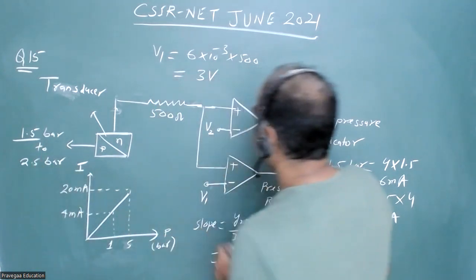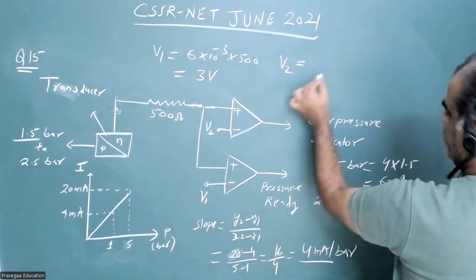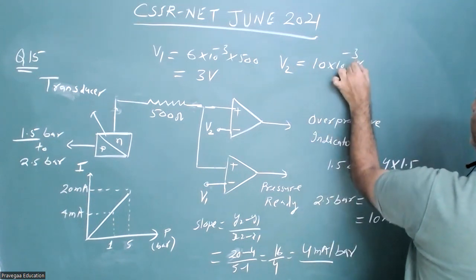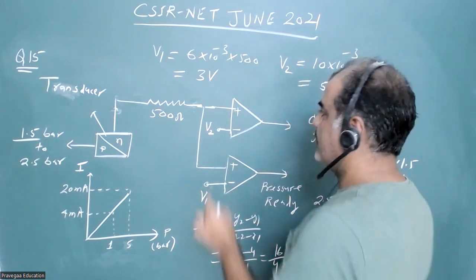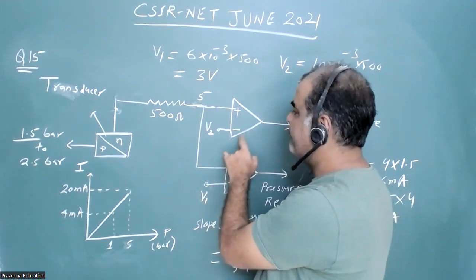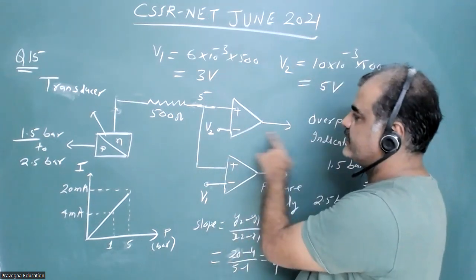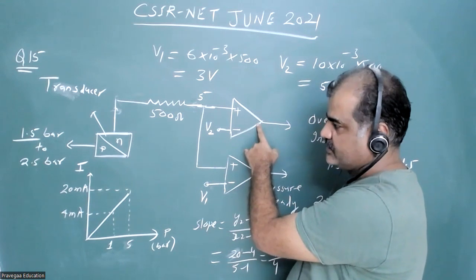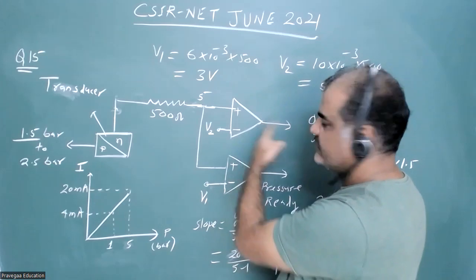For 2.5 bar, the voltage will be 10 milliampere × 500 ohms = 5 volts. As soon as the voltage reaches 5 volts, the output of the op-amp will saturate, indicating that this is an overpressure condition. The output is saturated and we cannot go beyond this limit.